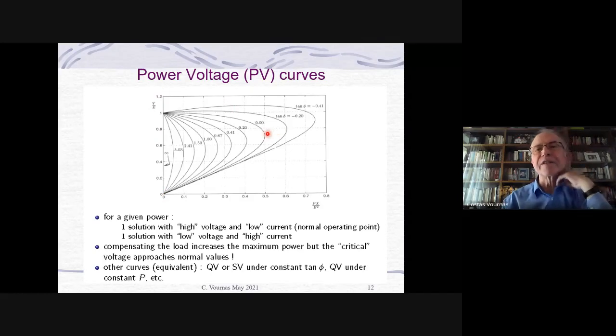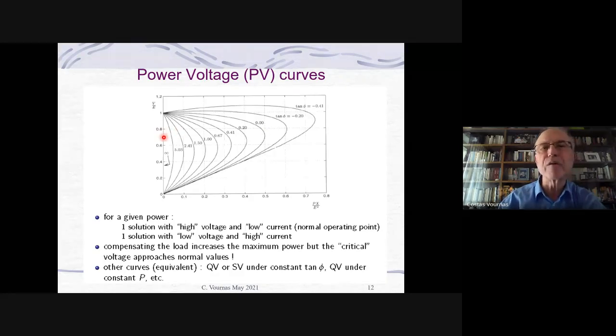If I take, for instance, the 0 angle, which is unity power factor, you can see I have a maximum power that's half of the short circuit power - 0.5 here, this is my maximum power. And here is the voltage where I have maximum power, close to 0.7 times the initial feeding voltage V. So I have a whole bunch of PV curves, each for a different power factor, or a different tangent of phi.